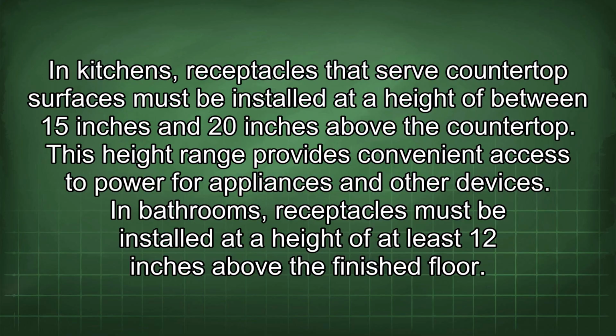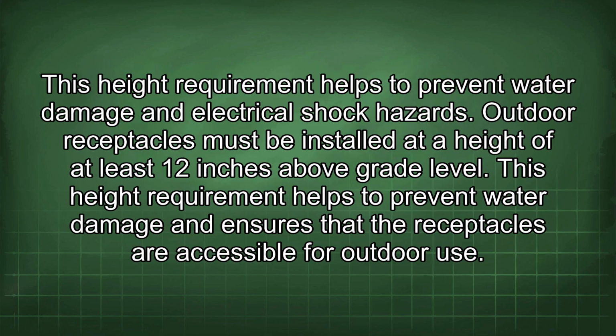In bathrooms, receptacles must be installed at a height of at least 12 inches above the finished floor. This height requirement helps to prevent water damage and electrical shock hazards. Outdoor receptacles must be installed at a height of at least 12 inches above grade level. This height requirement helps to prevent water damage and ensures that the receptacles are accessible for outdoor use.